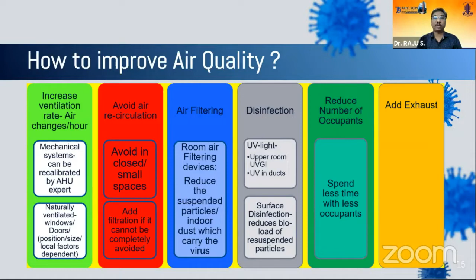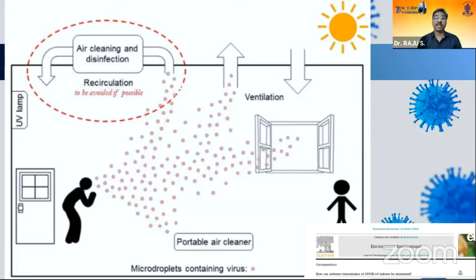This is a diagrammatic representation showing all the things that I just told you. If you have to use a recirculation unit, make sure that you add cleaning and disinfection in between the time it recirculates. That will help in reducing the load inside the room. Coming to the relative humidity and temperature, it's important that we maintain the relative humidity between 40 to 60.